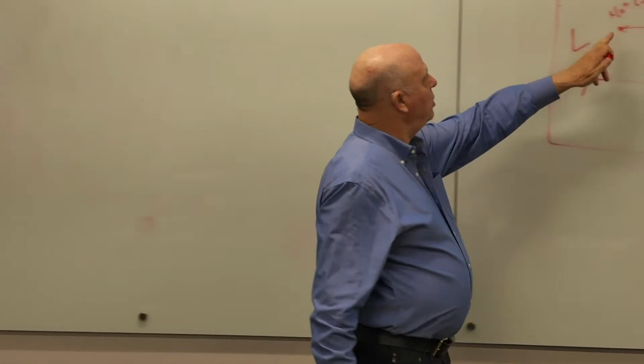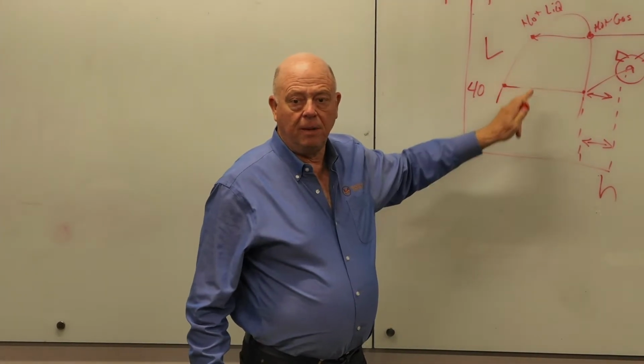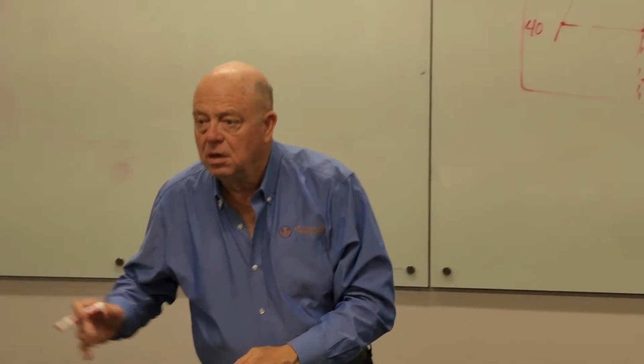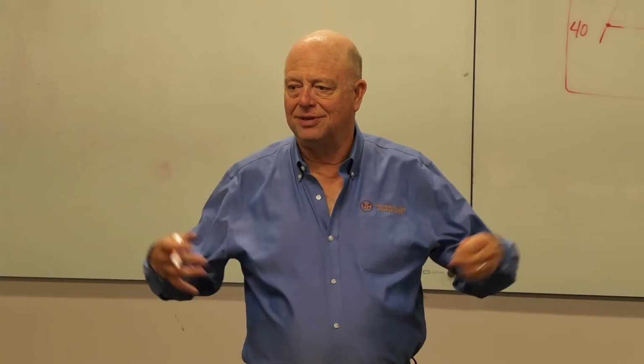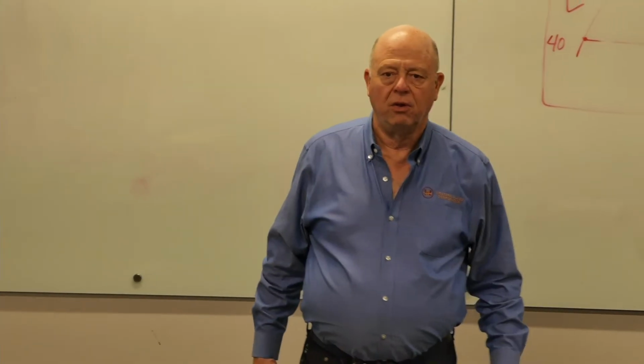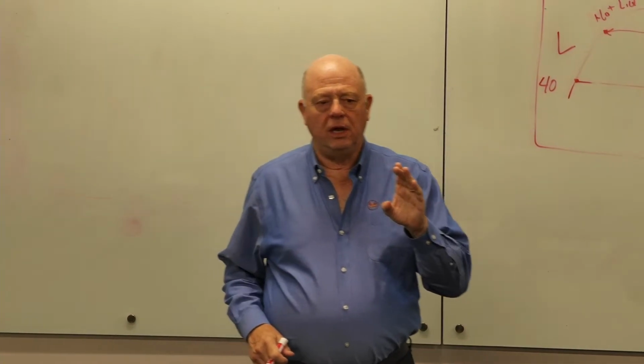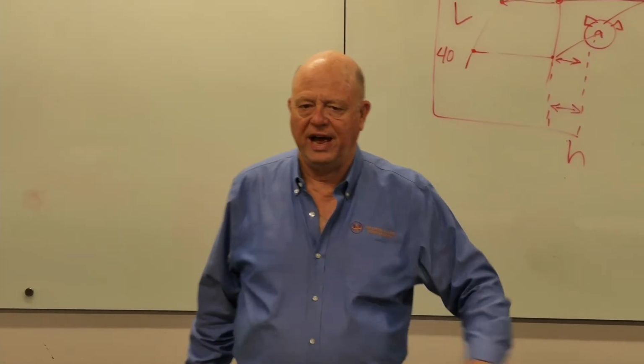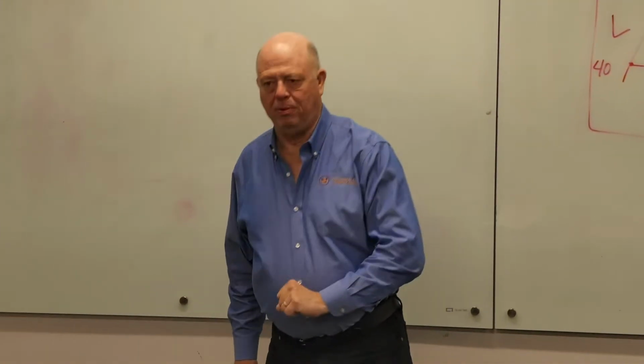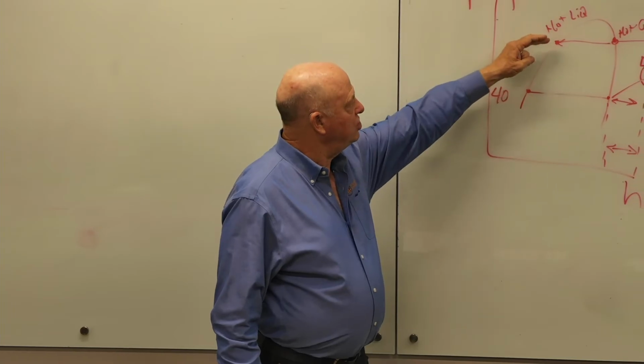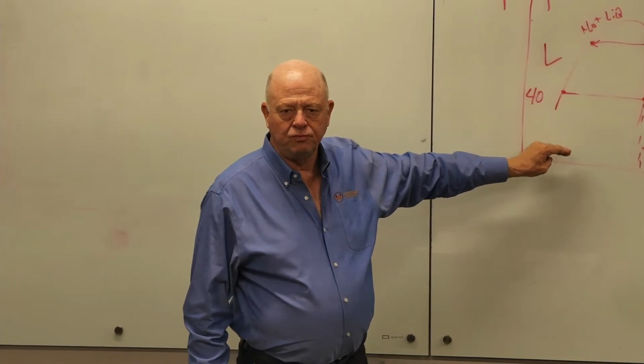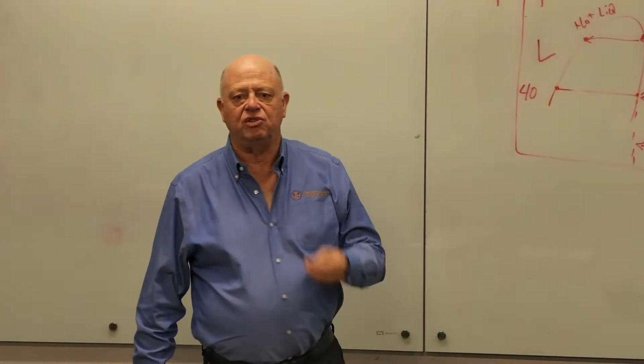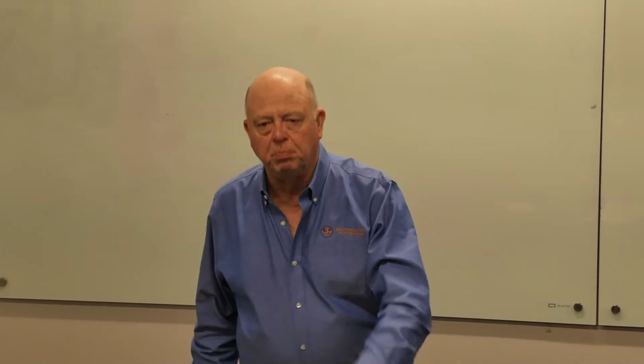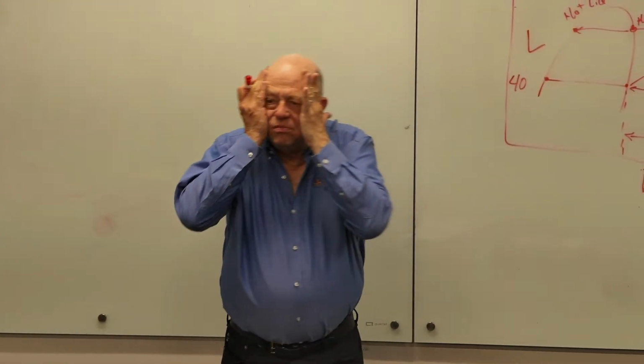Now, if we knew that we had 100% liquid, we could at that point put it through an expansion device, come back here, and a small part of that liquid would give up its liquid state to cool the rest of it. Depending upon who is teaching your physics class, some people will tell you that the expansion device is changing the pressure and therefore the temperature. Other people will tell you that the expansion device is causing a change in state which produces the temperature change. Both of those are correct. But it's a different way of looking at it.